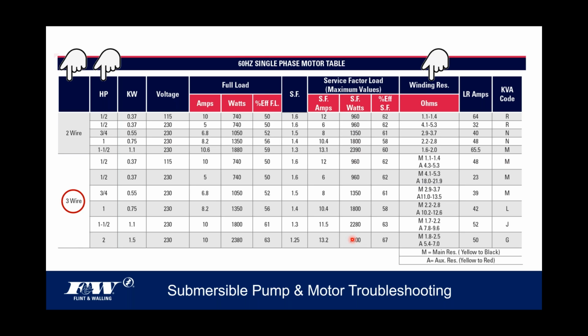Again, let's just take a 3-wire pump. Let's say it was 1.5 horsepower. I'm just using this as a virtual example. If I come across from that 1.5 horsepower 3-wire pump, I'm getting two sets of values. I'm getting an M value of 1.7 to 2.2, and an A value of 7.8 to 9.6. Now again, this is on a 3-wire motor. If I want to know what that M and that A is, I just drop down to the bottom of that chart, and it tells me: yellow to black is my M value, 1.7 to 2.2, and yellow to red is my A, 7.8 to 9.6.